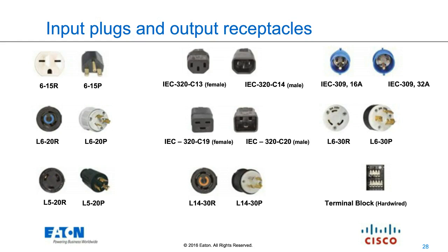So for most blade architectures, you'll be looking at that C19, C20 jumper to go off to the PDU, which of course then, Randy, will affect which PDU you need, because you're starting to need more C19s on your PDUs then. Absolutely, and since those C19s, they're unique in that they require a 20 amp breaker to protect them rather than the standard 15 amp breaker. So from a PDU design consideration, when we're building those high density PDUs, if we've got a PDU that's going to need 6 C19s, that's now 6 20 amp circuit breakers, that's going to impact the cord that we have to put on it. So now we're starting to look at really needing to bring possibly 3-phase power into that environment, just to provide enough energy or enough wattage to the PDU, ultimately to those power supplies.